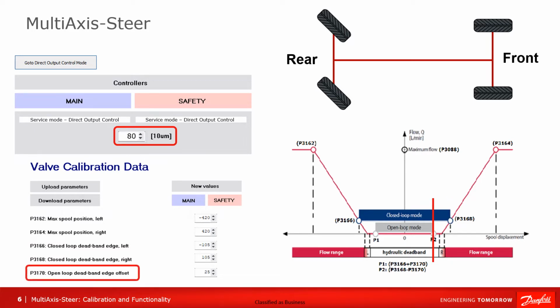The open loop deadband edge is the spool position when there is no flow to the wheels. This is entered as the open loop deadband edge offset and can be decreased from 25 but should not be increased.